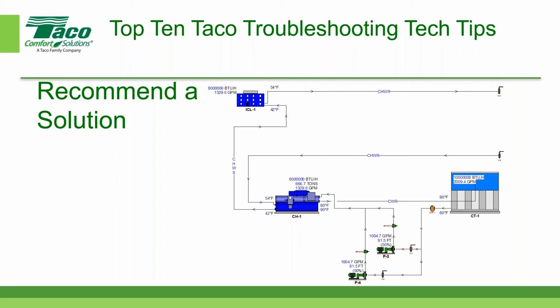Yes, the pressure gauge is measuring static pressure in the system, assuming that it was installed properly. And to get a good reading, the gauge needs to be connected in perpendicular to the water stream or the fluid stream. If you connect the gauge facing the flow and you're reading the total pressure, then you're reading the static pressure plus the velocity pressure. So Bryce clarified that was related to the comments about correcting for fluid velocity differences. That makes sense. Yes. So whenever you have a difference in outlet size versus inlet size, you have to correct for the velocity pressure if you're looking for the static pressure differential.